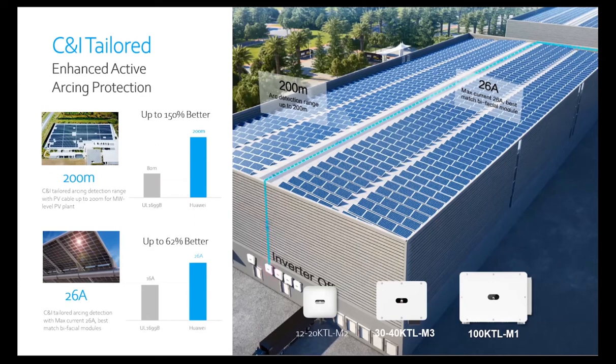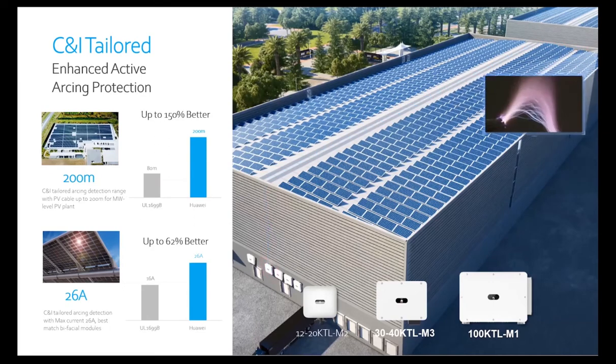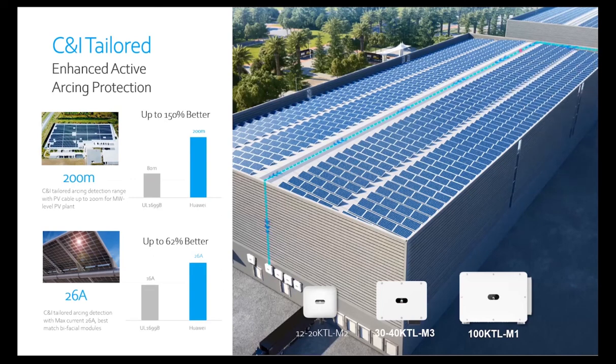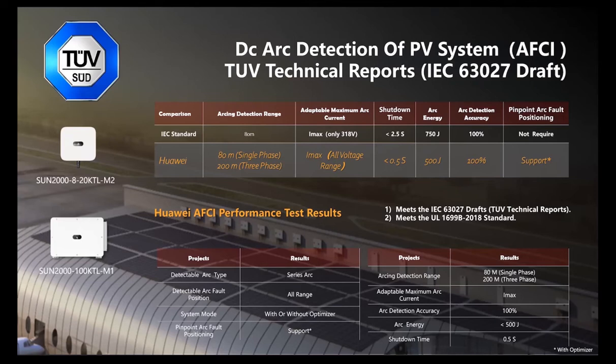So with Huawei technology, we are able to accommodate the active arc safety functionality and the alarm detection within the inverter itself of up to 200 meters and within 26 amperes. So this accommodates the high current PV modules that are becoming available in the industry, whilst also allowing a wide, flexible scenario of inverter mounting at long distances away from your PV array. Now, the DC arc detection of the PV system itself is called the arc fault circuit interrupter functionality. We have gone to a third-party standard, so TUV technical reports such as the IEC 63027 draft report are more than accommodated using the technology installed within the products mentioned on the left-hand side.